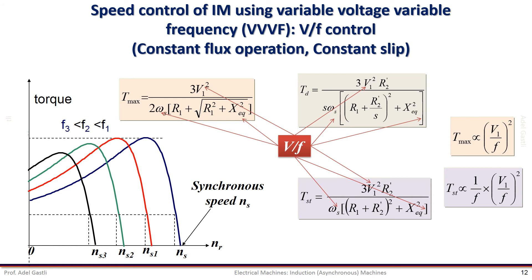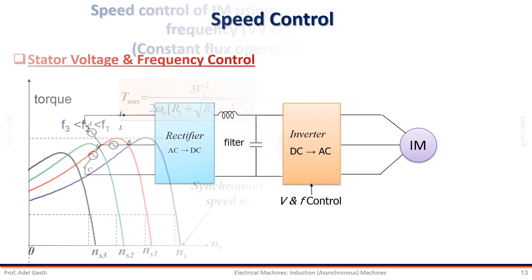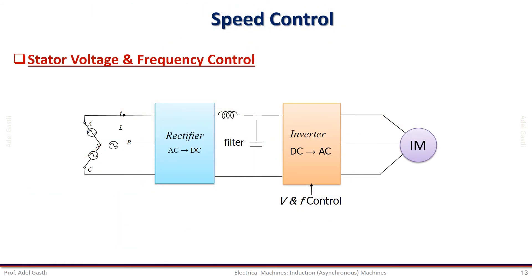This is considered an efficient speed control technique since the efficiency of the motor is not affected by the increase of the slip. The control of voltage and frequency can be performed using an inverter, which is a power electronic converter. From a fixed AC voltage source, we convert it to DC power through rectification using an AC-DC converter. Then the DC power is converted to a variable voltage and frequency AC power to feed the induction motor using the inverter. All these power converters are based on power electronic devices and circuits.